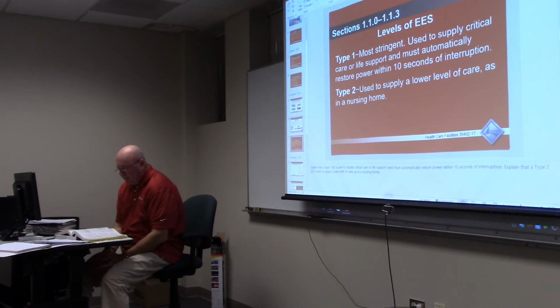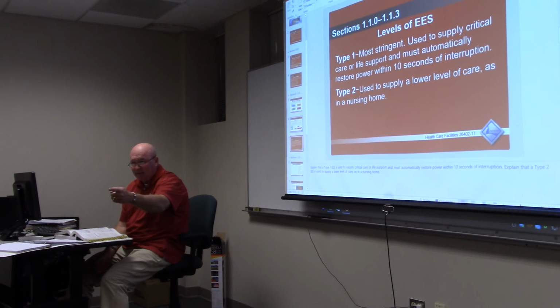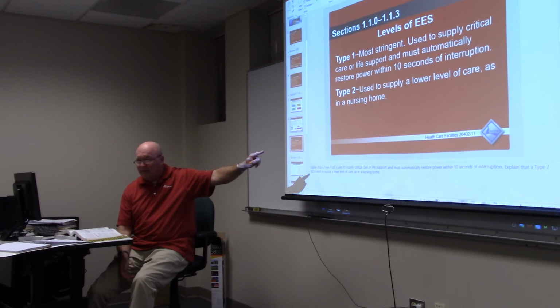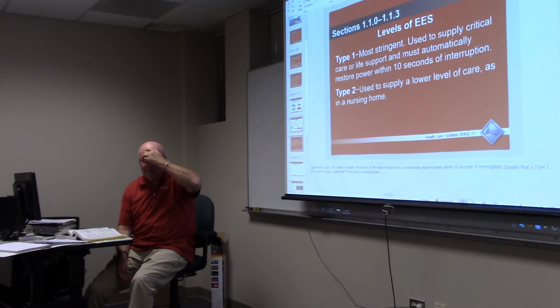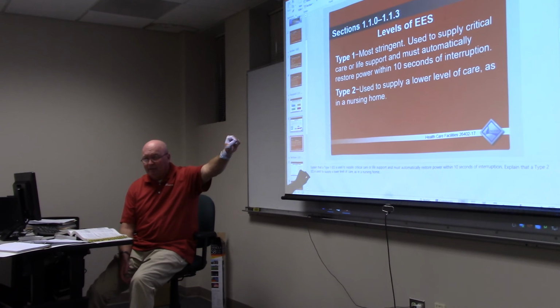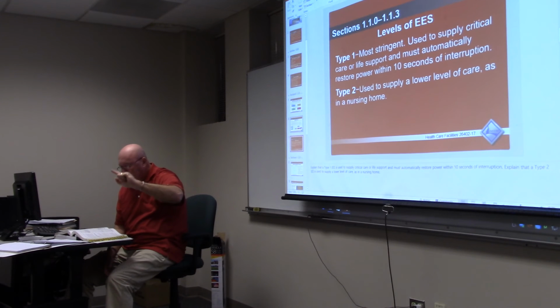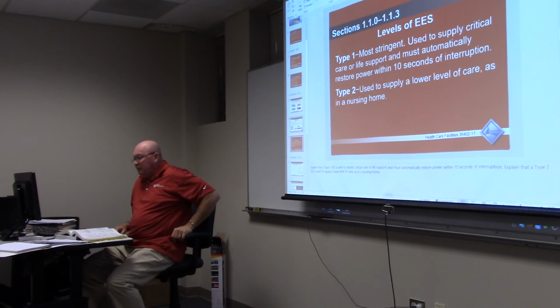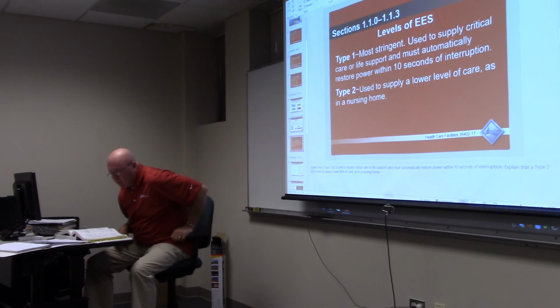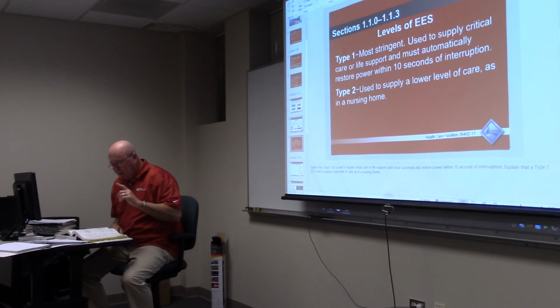So it says patient bed location. Each patient bed shall be supplied with two branch circuits. One from the critical branch, emergency system. That's exactly what we're studying here. Critical branch means it's going to have to come from an alternate source of backup power. So one of those has to be critical branch, and then one can be normal.